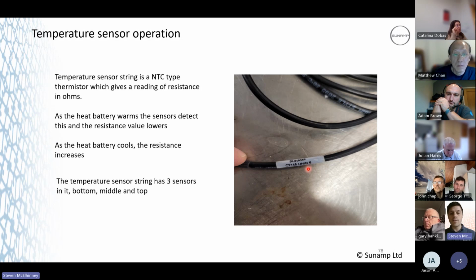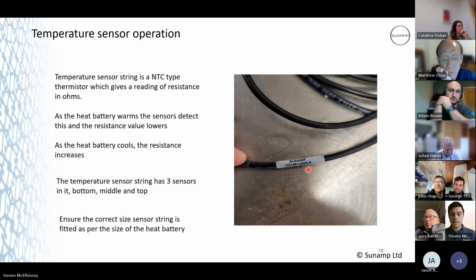So if you ever have to replace a sensor, just make sure you've got the correct size. Because if you fit one that's too long, it will never reach temperature. If you fit one that's too short, it's just going to overheat. So you have to make sure you've got the right sized sensor string, as it says there.